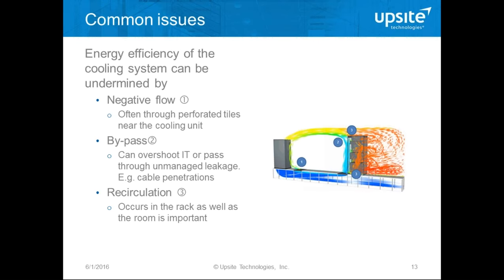Touching on what Lars discussed about bypass — we're trying to match cooling airflow between the cooling supply and the rack. But there are a few other things that can go wrong. We can get negative flow through the raised floor through a tile near the cooling unit, which is commonplace. We want to avoid hot air going back into the cold airstream — that's negative flow. We want to avoid bypass, and we also want to avoid recirculation, which is hot air going back into the cold airstream in the room.